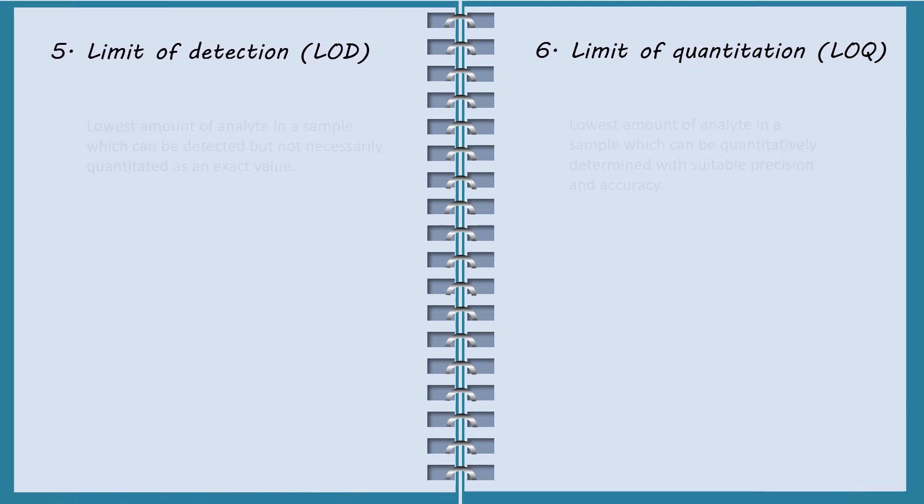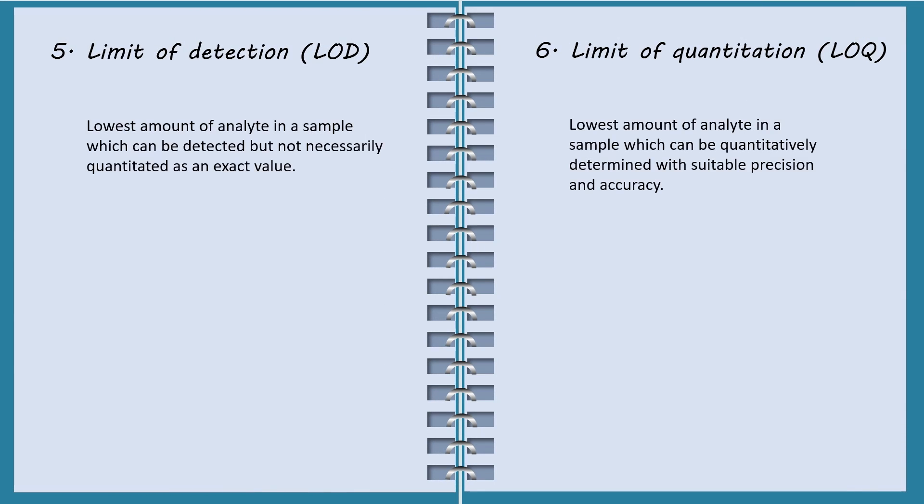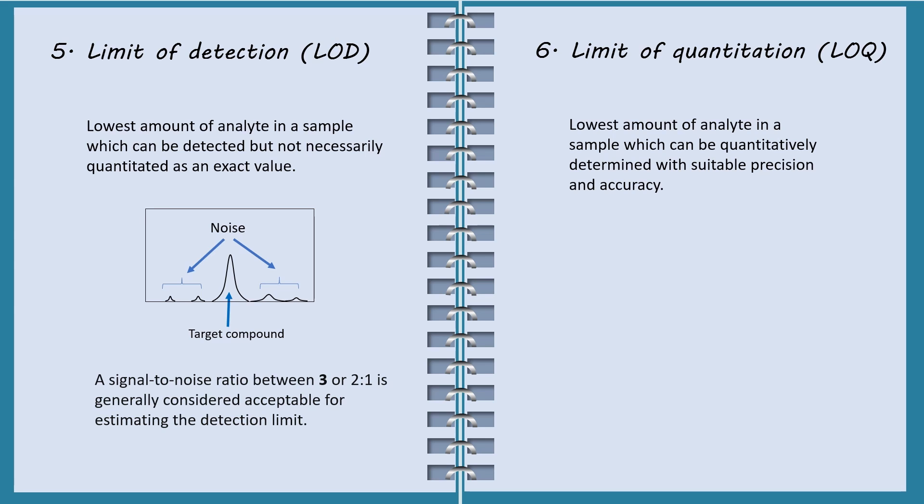Limit of detection, LOD and limit of quantitation, LOQ are two parameters that must be included in the validation report. This is target compound. This is the noise. Signal-to-noise ratio is often used for estimating LOD and LOQ. A signal-to-noise ratio of 3 is generally considered acceptable for estimating LOD. A typical signal-to-noise ratio of 10 is acceptable for estimating LOQ.